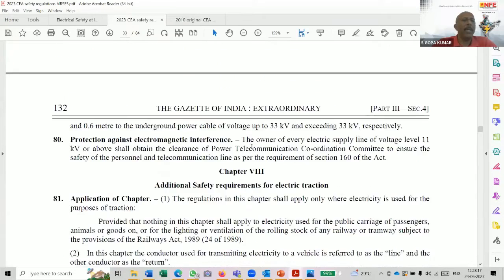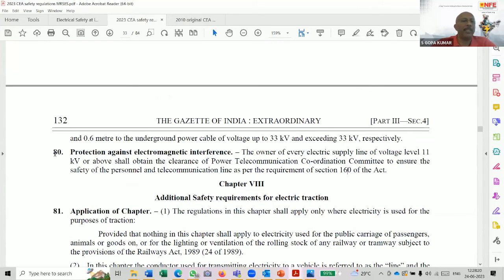So, regulation number 80 is protection against electromagnetic interference. The owner of every electric supply line of voltage 11 kV and above shall obtain clearance of the Power Telecommunication Coordination Committee to ensure the safety of personnel and telecommunication line as per the requirement of section 160 of the Act. Can anybody answer on this? See, this is a requirement as per the Telegraph Act. That section is from that only, I think. But such clearances are never taken. I haven't seen such clearances being taken. I have attended a few of the meetings of this PTCC, but most of the things just remain on paper. So that's not being followed.